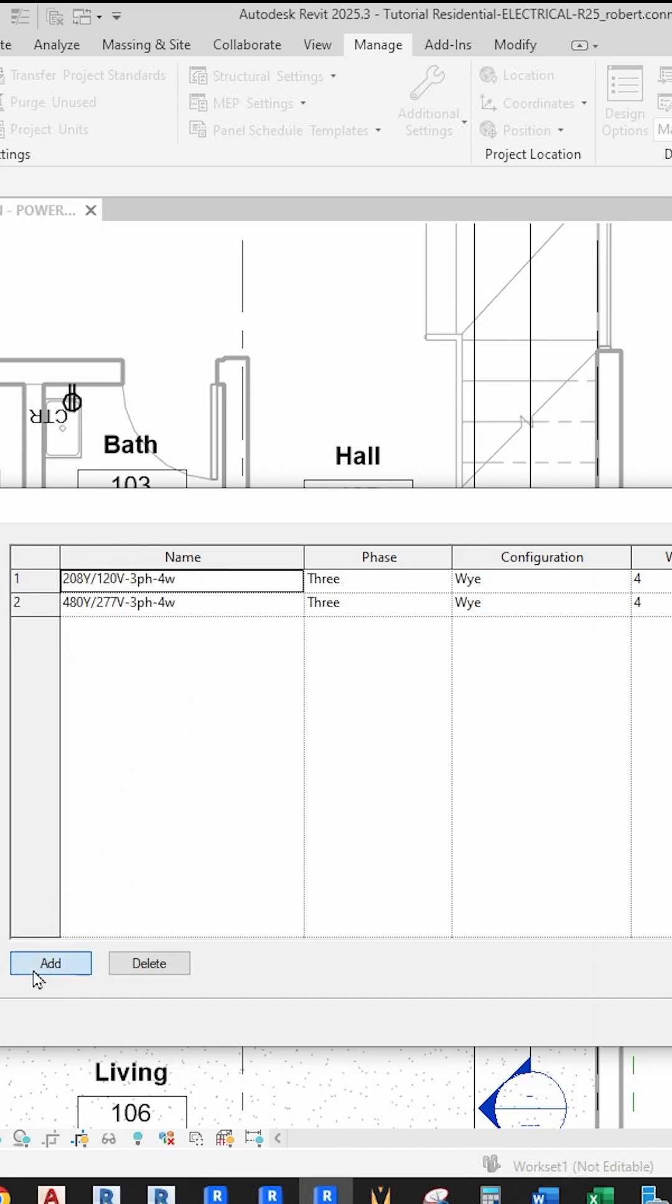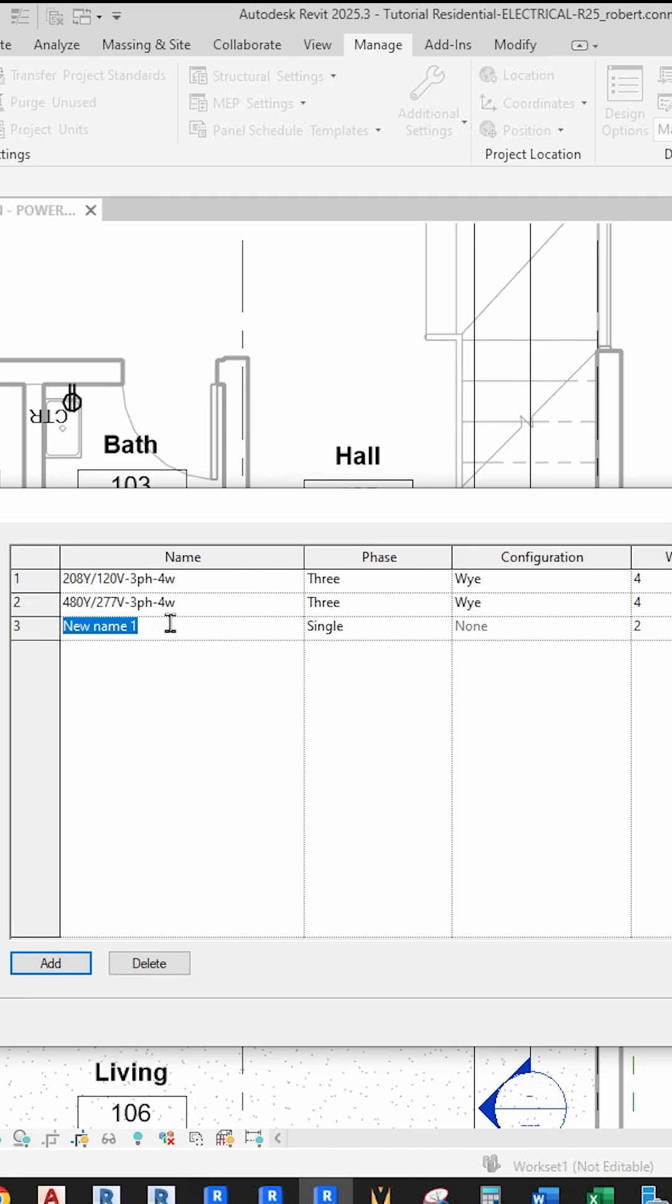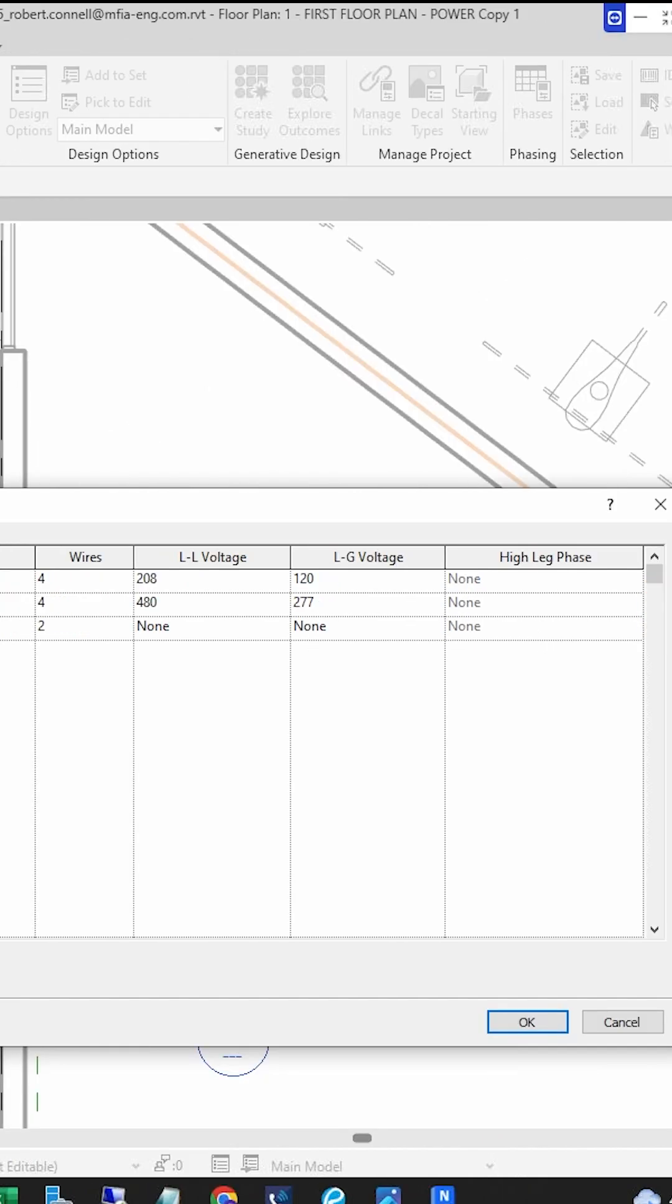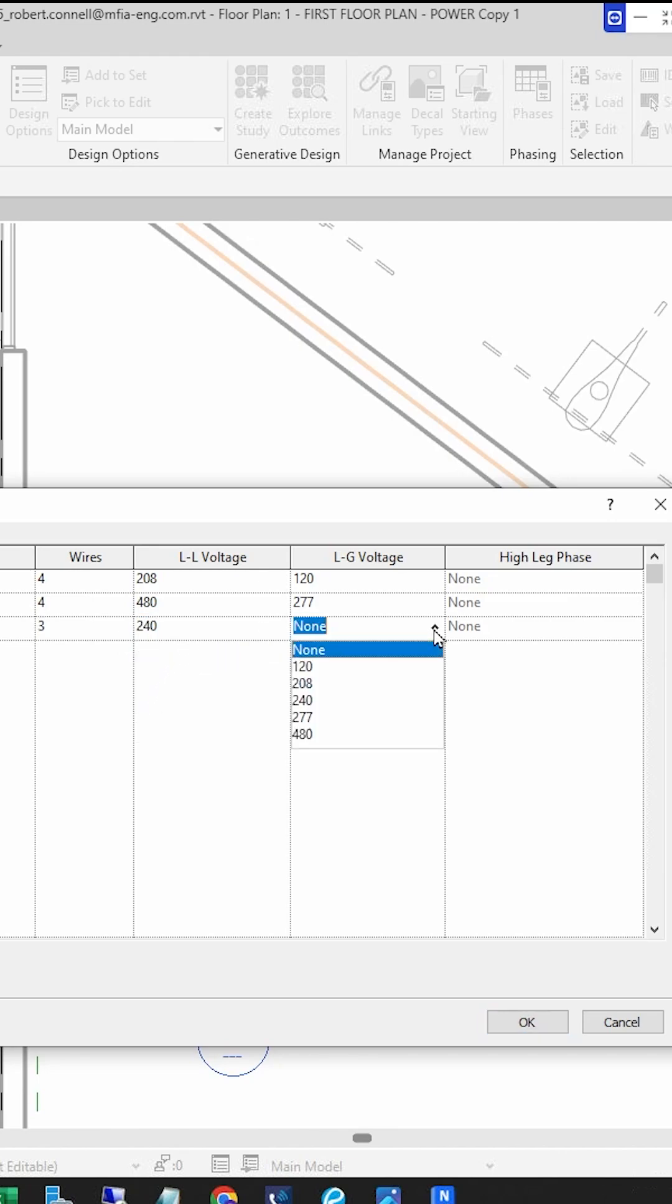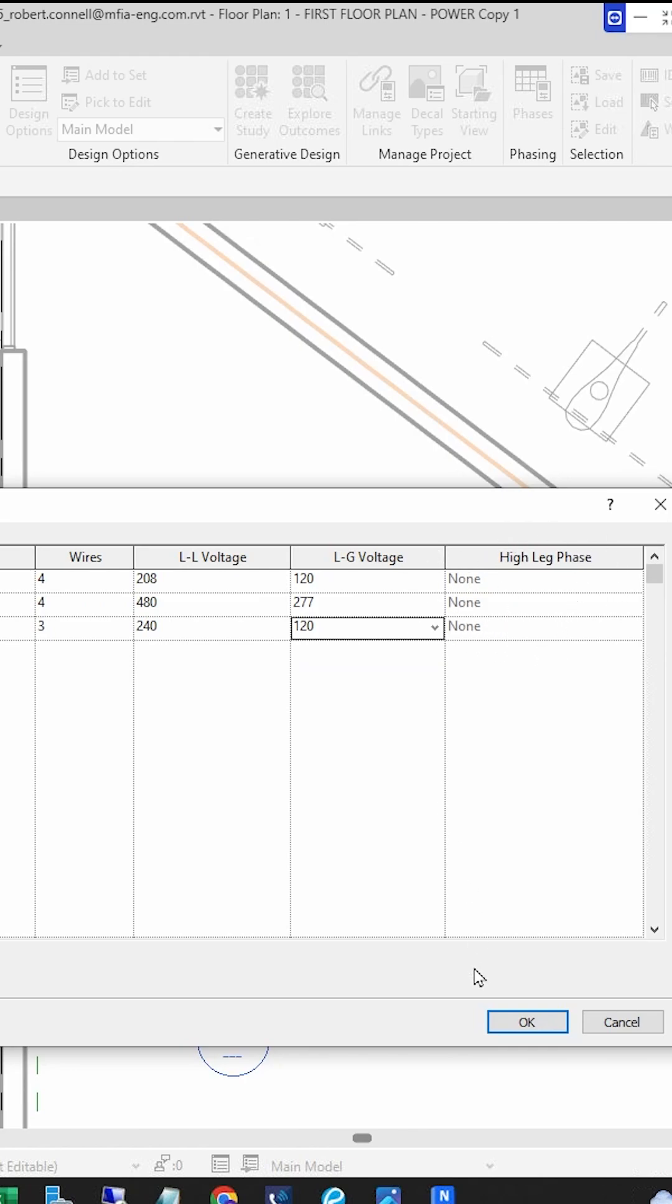At the bottom, click on Add. Then enter the system name 120/240 Single Phase. The phase is single. The configuration is none. It's not a wye or a delta. Wires is three since we want two hots and a neutral. Line to line voltage is 240. The line to ground or line to neutral is 120. And then high leg phase is none. We don't have that here. Then click OK.